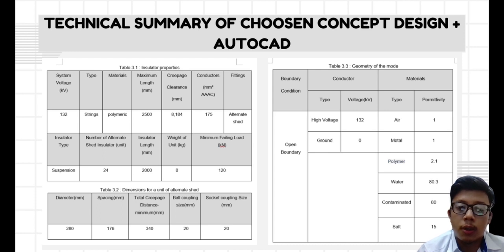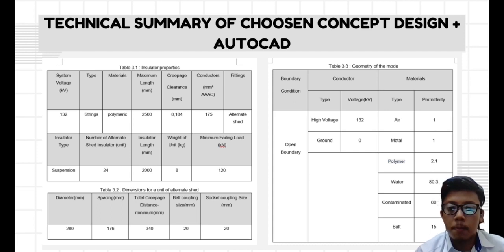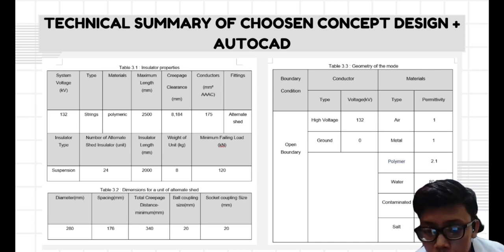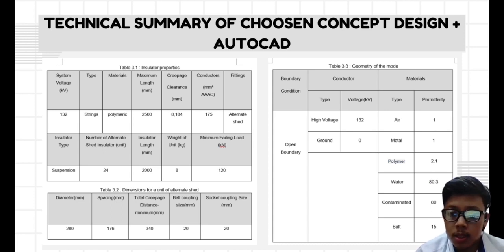Okay, for the first column, we have the boundary condition, which is an open boundary. For the next column, we have conductor type and voltage. For the type, we have high voltage and ground. For high voltage, we are going for the max, which is 130 kV, and for ground it is zero. And the last column is material. We have type and permittivity. For the type, we have air, and the permittivity for air is 1. Next is metal. The permittivity is also 1. And the third one is polymer. The permittivity is 2.1. Next, water. The permittivity is 80.3. The second one is contaminated. The permittivity is 80. And the last one is salt. The permittivity is 15.